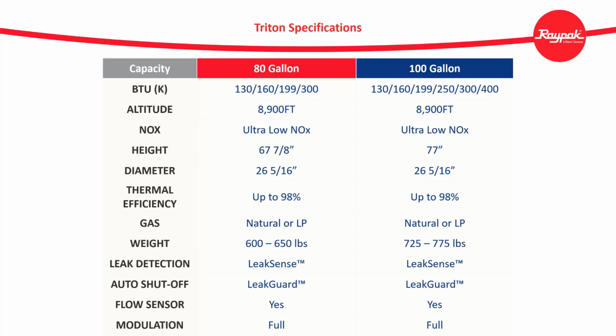There was a lot of voice of customer done in this product, and one of the questions asked was what was more important, being skinny or having that extra 19 gallons. The overall consensus was to be thinner. At 400 BTUs, we are 7 inches narrower than the A.O. Smith at that same BTU level, and that will get us into a lot more places. Ours is 100 gallons, where the A.O. Smith is at 119 gallons, but with only 4 to 6 gallons of recovery rate given up.